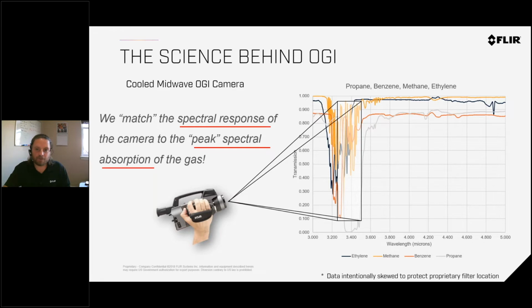So what we do is we find out where these gases lie in the spectrum and their transmission. Then we tune the lenses in our cameras to where those transmissions are low, because where those transmissions are low, that's when it's going to appear to be smoke, because we're not seeing the panel or the substation or whatever it is behind that. We see the smoke instead.